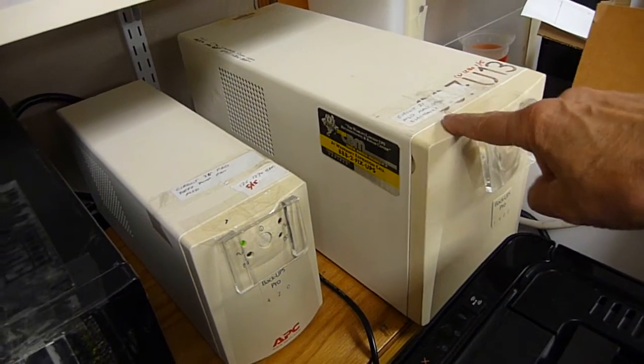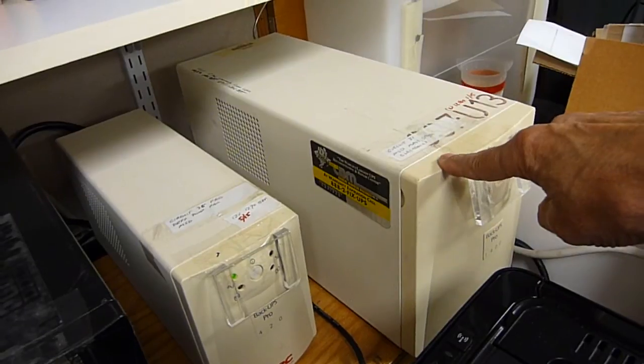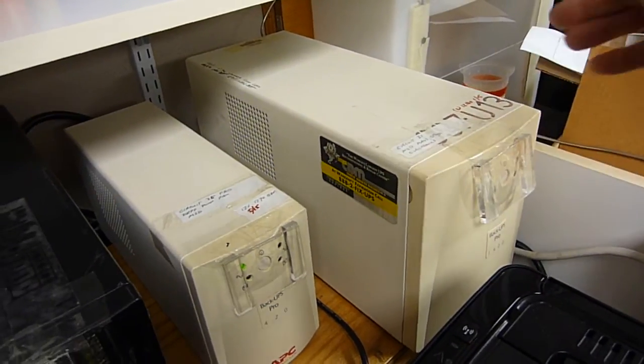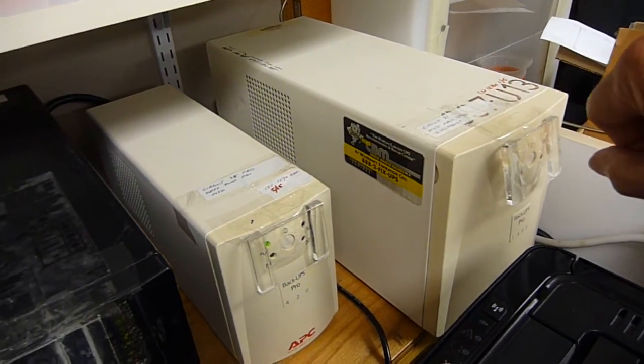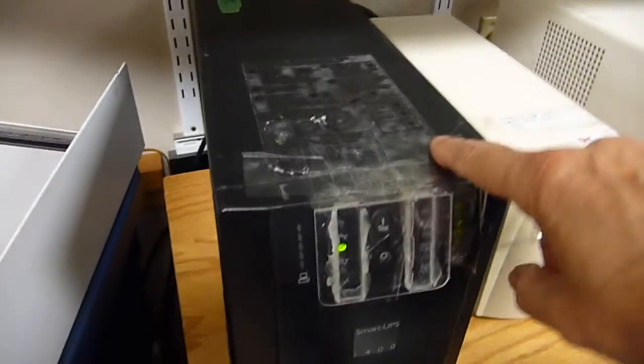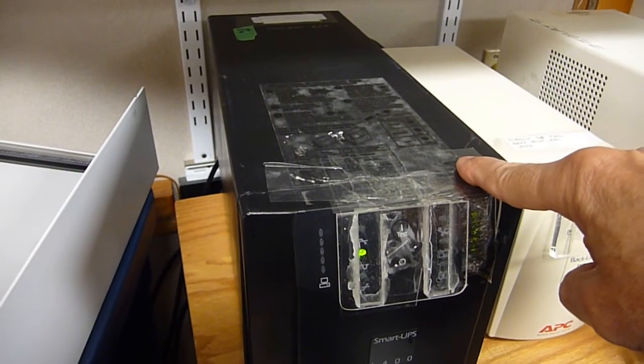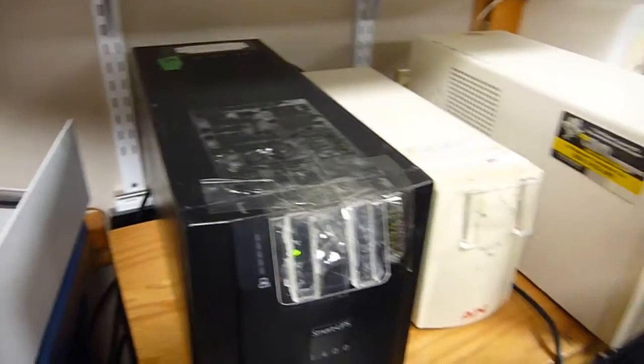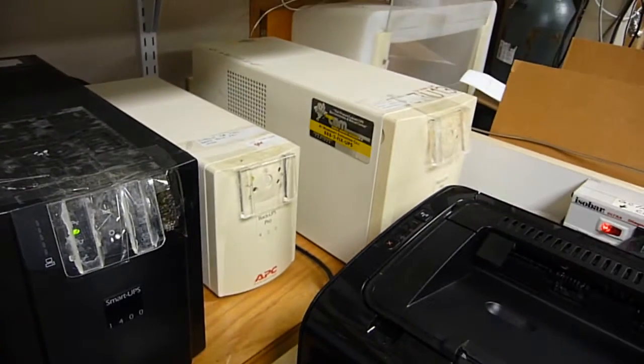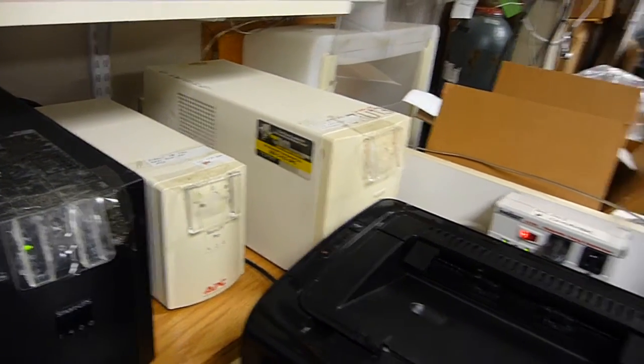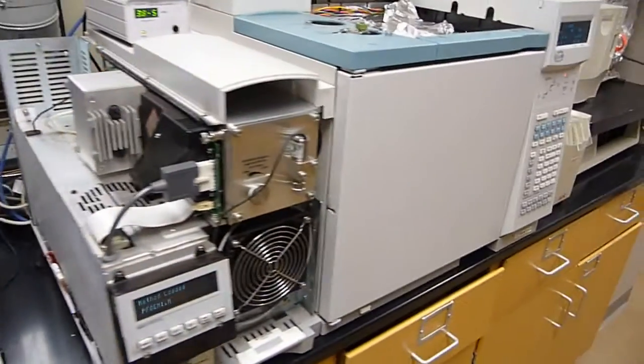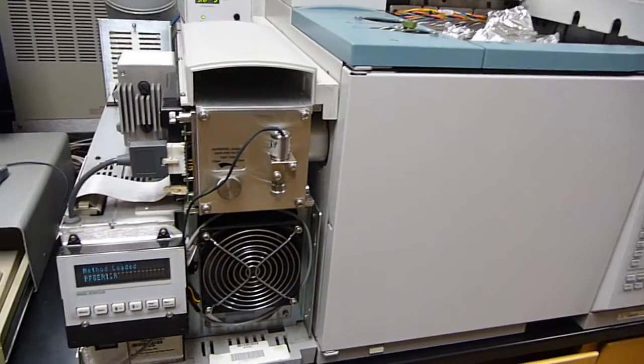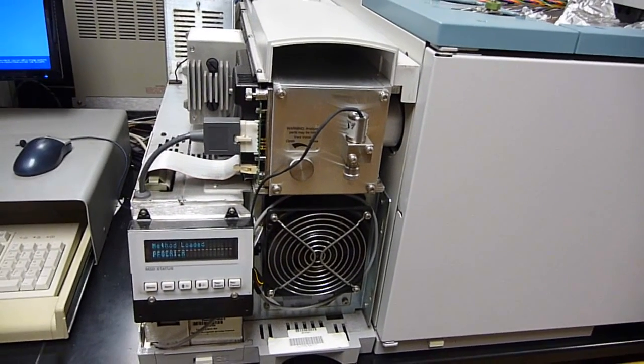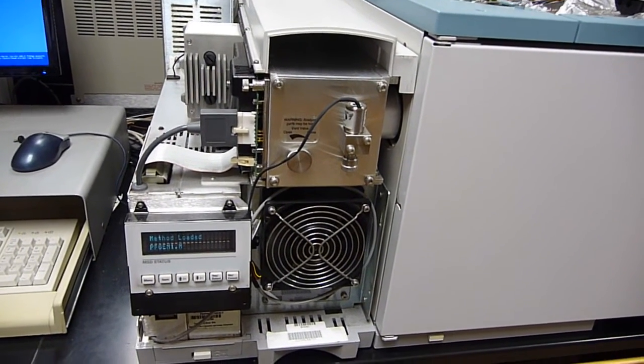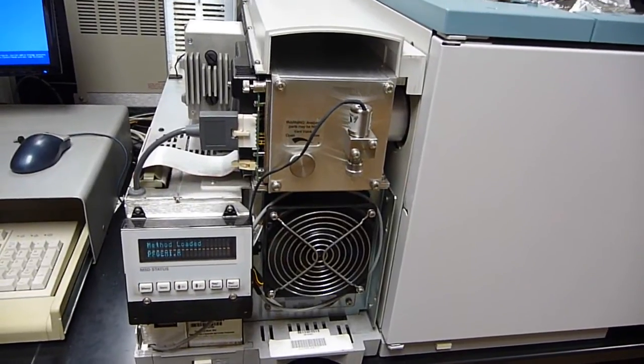Third UPS is for the MSD electronics. It's nice stable voltage, cut out the spikes. Fourth UPS is for the computer. Right. You're not going to have a cheap UPS big enough and cheap enough for the GC. The idea is for it to survive a power outage without backstreaming.